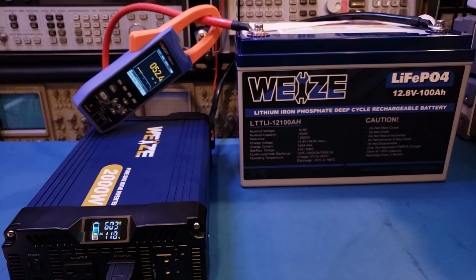It looks like right around 600 watts, the fan kicked in. And right now we're right around the maximum discharging current, 120 amps, dissipating roughly 1400 watts. Let me keep increasing. Remember, this inverter is rated for 2000 watts, so let's see if we can get close. Right now it's right at 2000 watts, and the discharging current is at 200 amps.